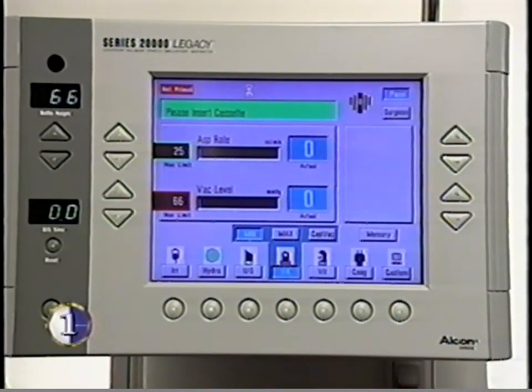The surgeon asp setting of these modes allows linear control of the aspiration flow rate with fixed vacuum limits. The surgeon vac setting allows linear control of vacuum limits with fixed aspiration flow rate. The third IA submode is capsule vacuum for vacuuming the surface of the posterior capsule following cataract removal. Aspiration rate and vacuum level are the primary parameters. Only panel control is enabled in the cap-vac submode.